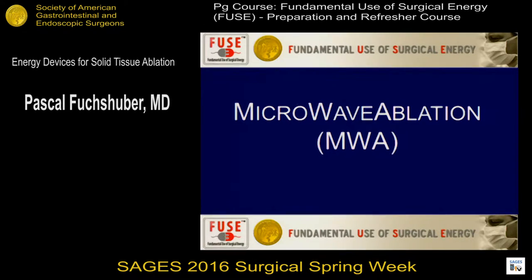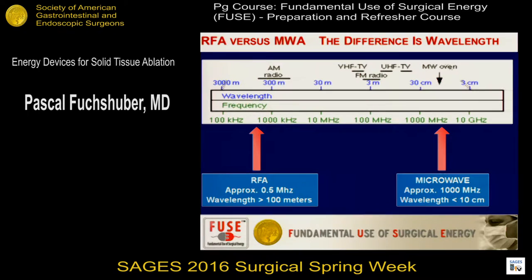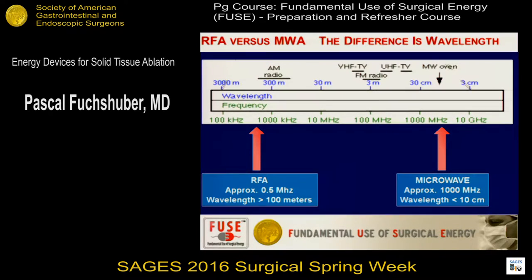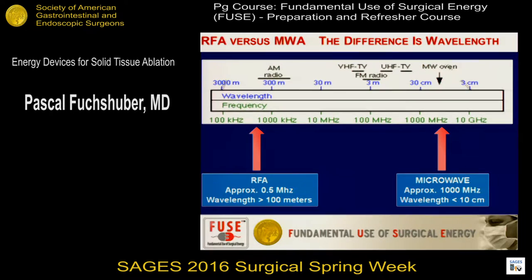Now let me switch to microwave ablation. The main difference between radiofrequency and microwave ablation is the frequency at which these systems work. Microwave is also alternating energy, but at 1,000 megahertz — essentially 1 gigahertz, or 1,000,000,000 hertz — versus 500,000 hertz for usual alternating current. So we are in the microwave oven range of energy. A key concept is that the wavelength is very different: in radiofrequency energy, the wavelength is greater than 100 meters — hundreds of times longer than the electrode used — whereas in microwave, the wave is about the size of the tip of the electrode.